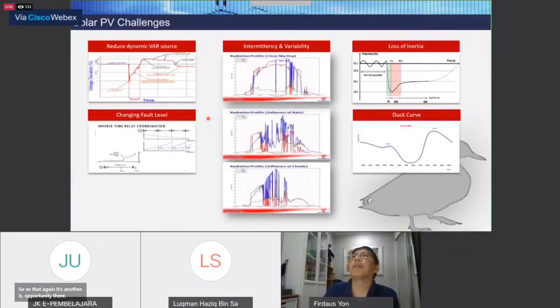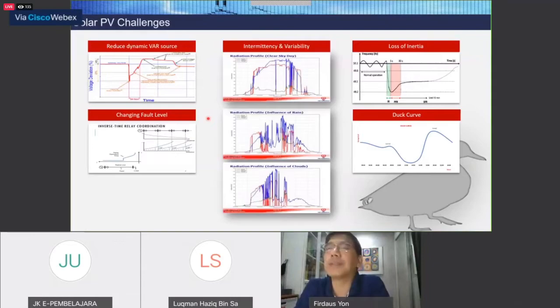Right, so these are the solar PV challenges. Left hand side is about reduced dynamic VAR source, being able to support voltage. There's an issue also with voltage, especially for solar connected on the distribution side, because of the intermittency of solar, it goes off and on, off and on. You will have disturbances on the voltage on the distribution end.